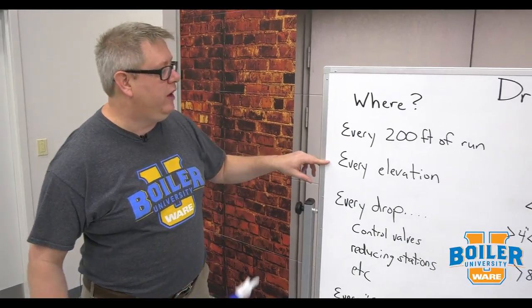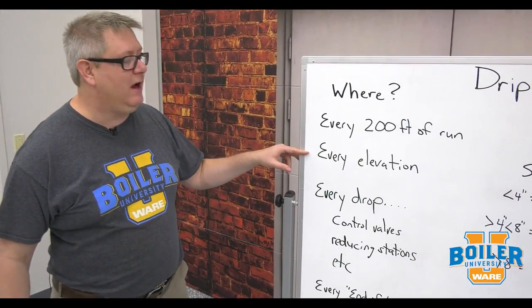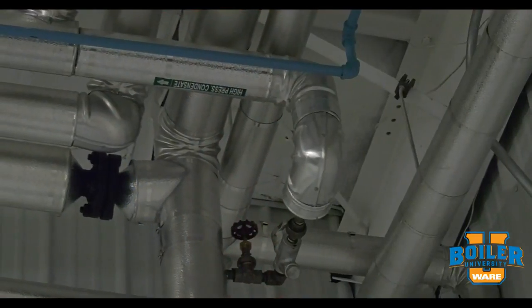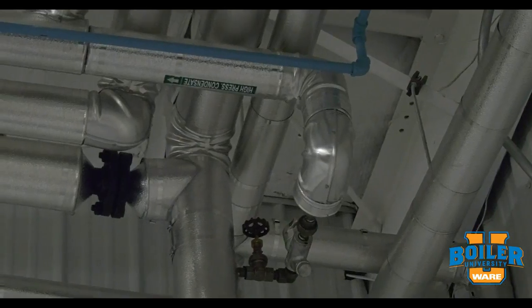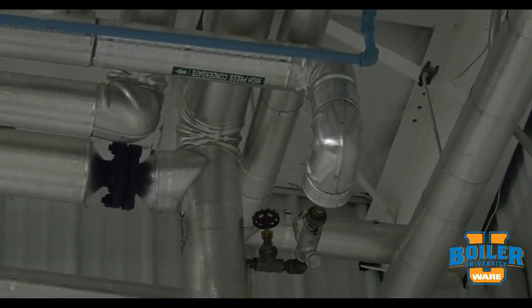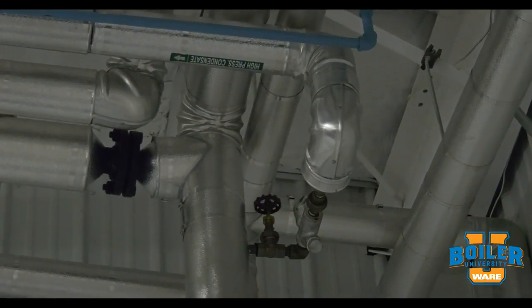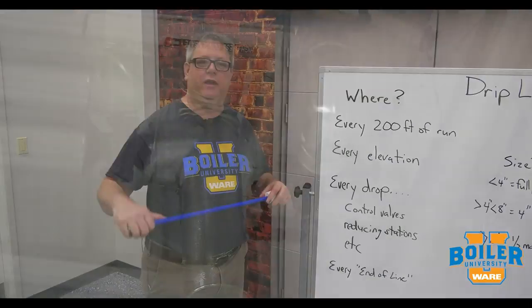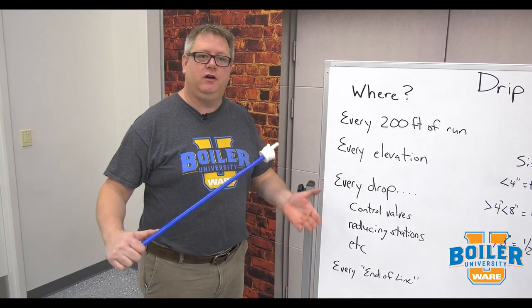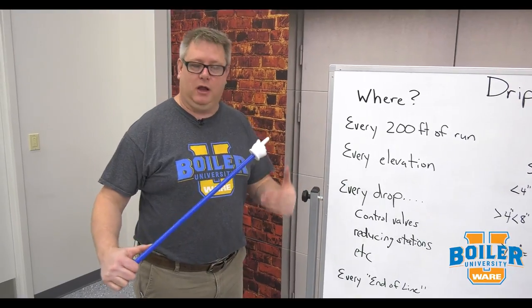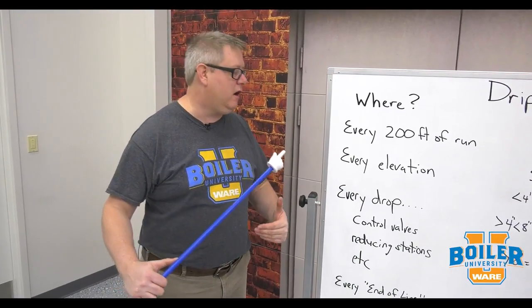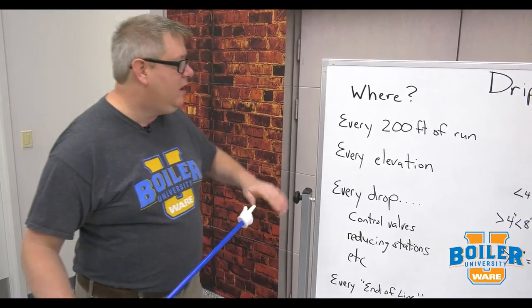We need to put a drip leg every time the steam line elevates, because condensate doesn't want to go up with the steam. By putting a drip leg there to capture it, it's a great point to collect and clear that condensate.